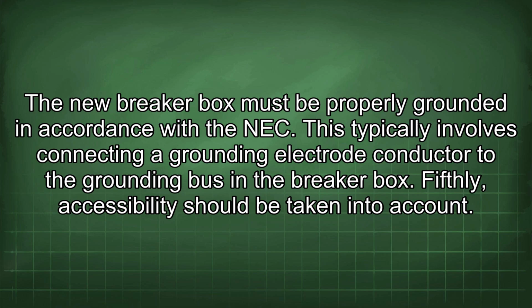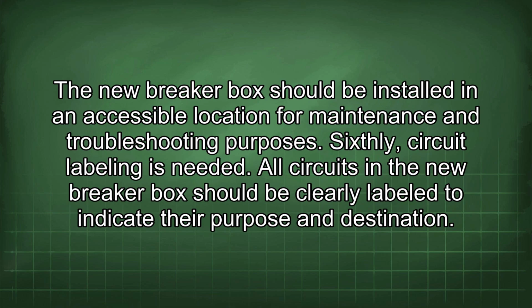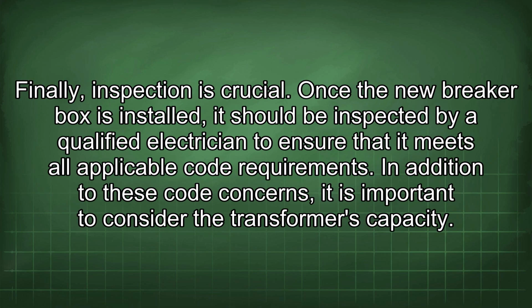Fifthly, accessibility should be taken into account. The new breaker box should be installed in an accessible location for maintenance and troubleshooting purposes. Sixthly, circuit labeling is needed. All circuits in the new breaker box should be clearly labeled to indicate their purpose and destination. Finally, inspection is crucial. Once the new breaker box is installed, it should be inspected by a qualified electrician to ensure that it meets all applicable code requirements.